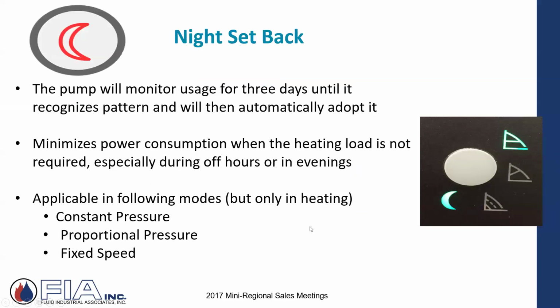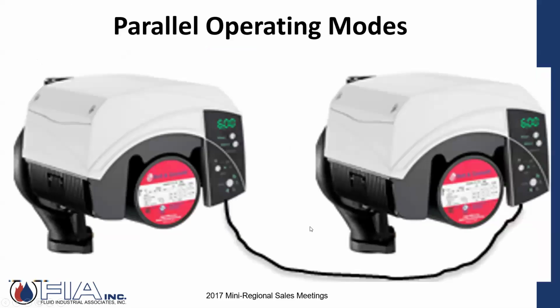Constant pressure is another mode. Then there's night setback, just taking that energy efficiency further; they'll represent it by having a moon. If the onboard temperature sensor in the pump senses a substantial drop in temperature, indicating night setback, it says, hey, I'm going to take that speed control and drop it even further.